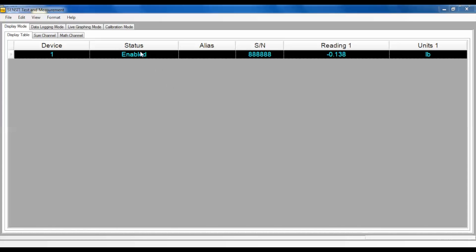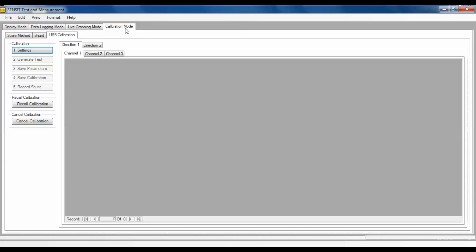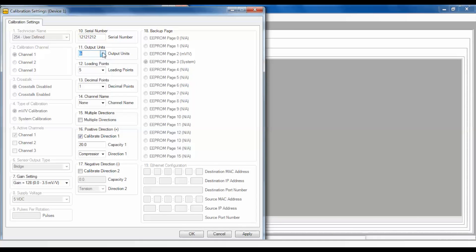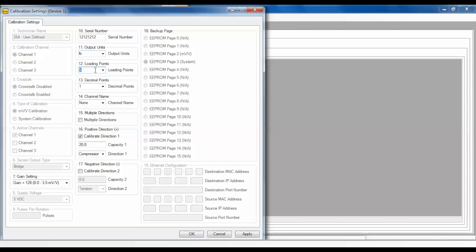In the SENSIT software, click on the calibration tab to enter into the calibration options. In the calibration section, choose the calibration sub-tab to go into the system calibration. Next, click the Settings button and enter the correct parameters into the calibration settings pop-up window. Enter in the serial number for the sensor calibrated to the USB device in the serial number window. This serial number will be stored in the USB device as a reference. Next, select your output units and enter the number of load points you're going to use to calibrate your sensor.